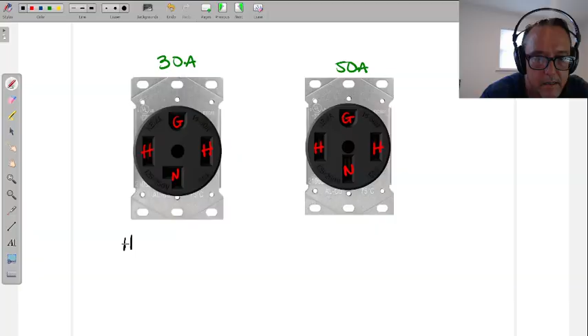We always want the neutral in play, and we want to check 120. I'm going to put here twice, like was pointed out yesterday. If you do a hot to neutral check, sorry let's do the neutral, and you have it here, you also have to do a neutral to that other hot as well, and make sure you have it there. So because there are two hots to this, we want to do the check for voltage twice.